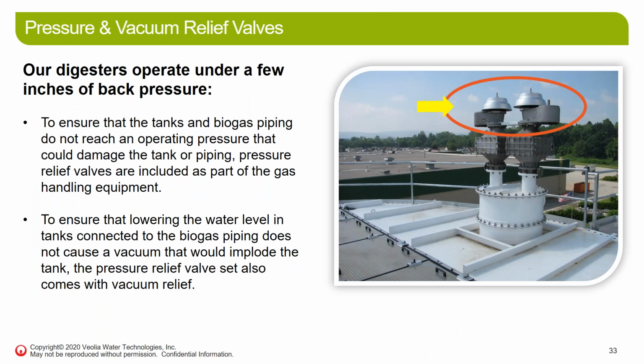PRVs are very important pieces of equipment that always need to be maintained during operation and during times of downtime. Typically our systems run under, you know, 12 inches of back pressure. So these are very important pieces of equipment to prevent the system from being overpressured or damaged by gas pressure buildup. Also vacuum relief: these ensure that when you lower the water level, we don't cause a vacuum in the tank or the piping system that would cause damage. So we always provide pressure and vacuum relief on tanks to prevent vacuum failures on tanks or the deck itself up there on the top.